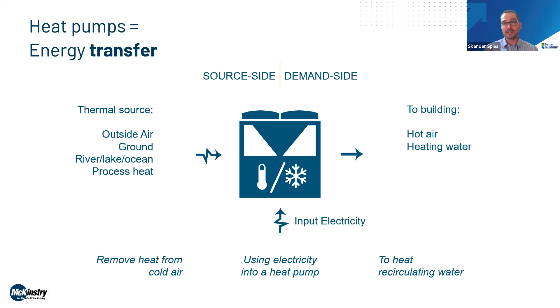The reason this is efficient, the reason we want to do this a lot, is that the refrigeration cycle is capable of moving more heat than it actually consumes in the electrical energy used to power the cycle. Many of you with some experience know the first cost of the equipment can be higher per unit of capacity installed. Sometimes there are other constraints, which we'll discuss later, around electrical capacity or the amount of space you have to install the equipment. But generally these are the key drivers: we're trading off efficiency with some amount of first cost.